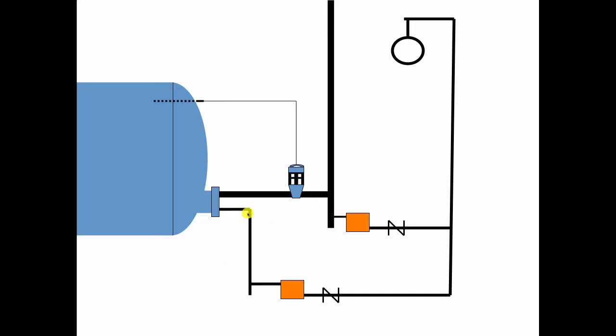So now the steam condensate is going to flow back into that trombone-like bayonet heater and the next time this regulator opens you're going to get a water hammer inside that and it's going to cause that same problem we looked at earlier. It's going to bust the tube.